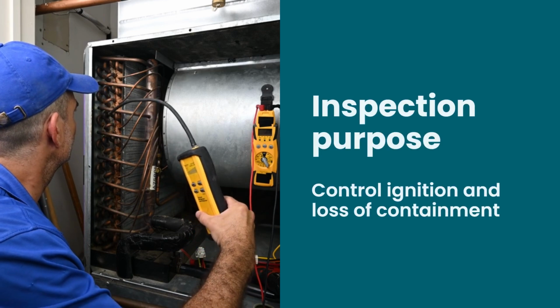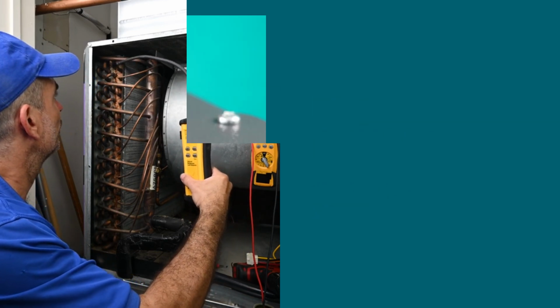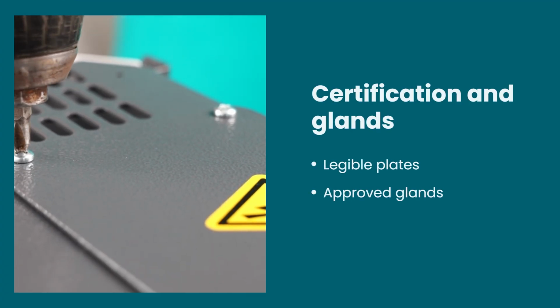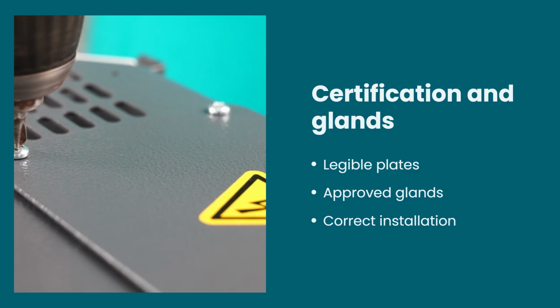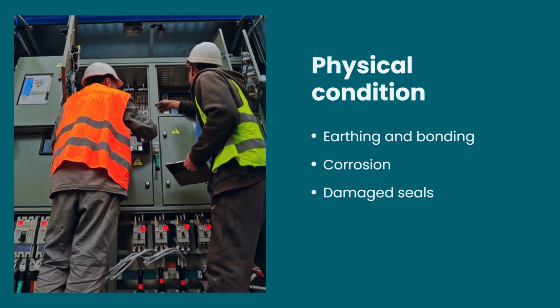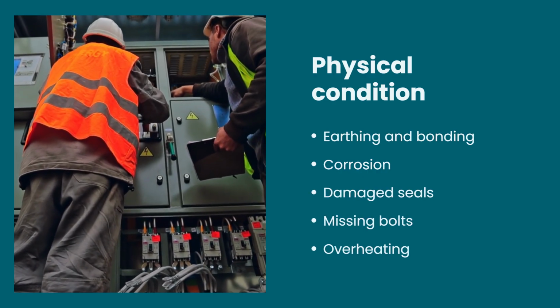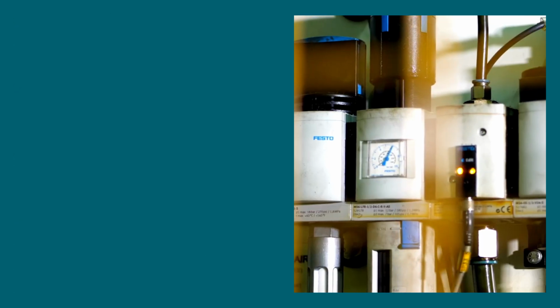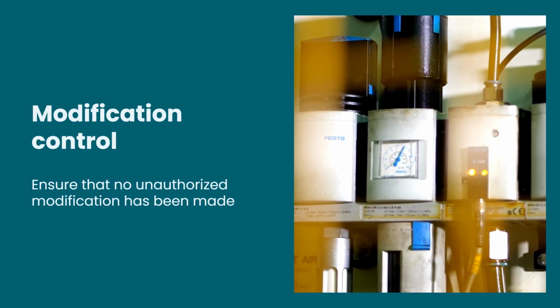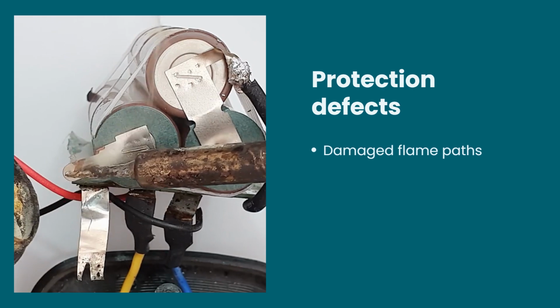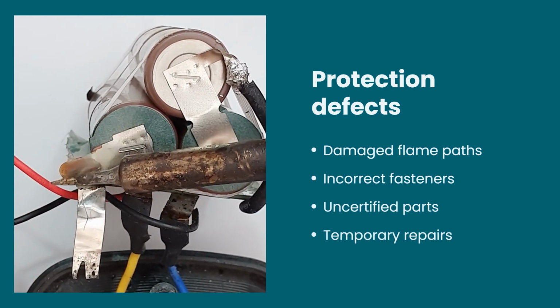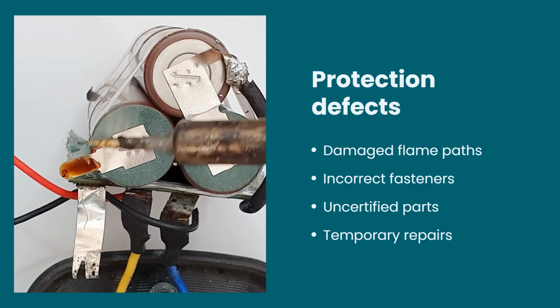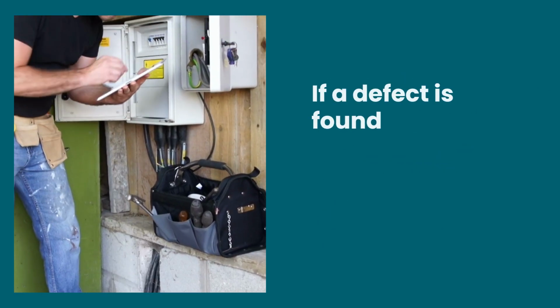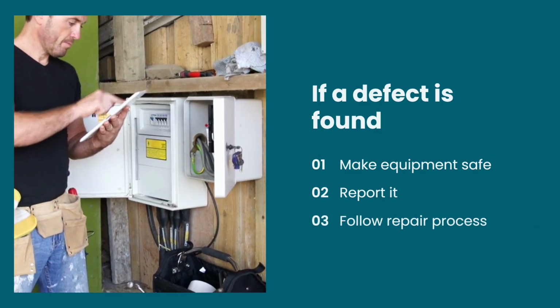Inspection is a direct control against ignition and loss of containment. Confirm that certification plates are legible and approved, and cable glands are correctly installed. Verify earthing and bonding, and look for corrosion, damaged seals, missing bolts, cracks, and overheating. Confirm temperature limits and ensure that no unauthorized modification has been made. Damaged flame paths, incorrect fasteners, uncertified parts, and temporary repairs can compromise protection. If a defect is found, make the equipment safe, report it, and follow the approved repair process.